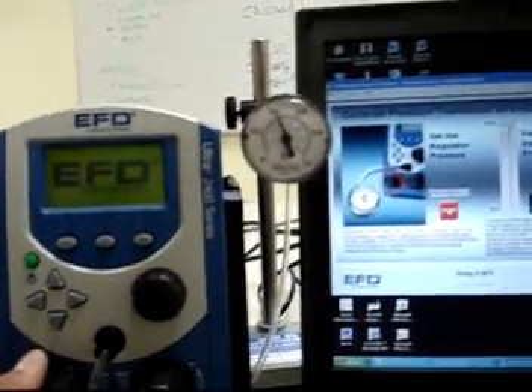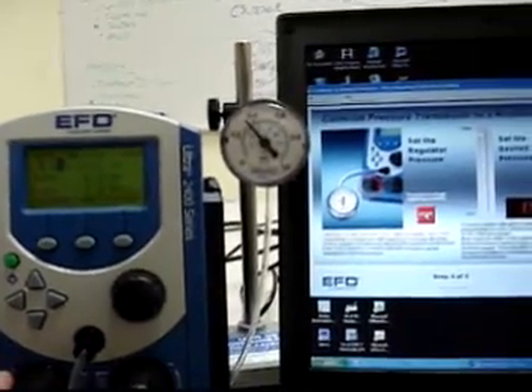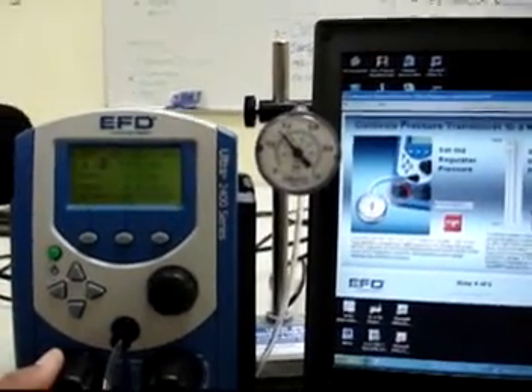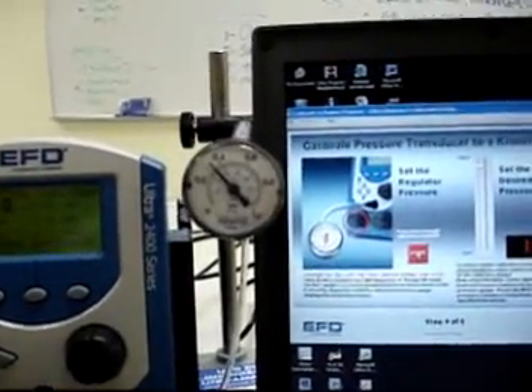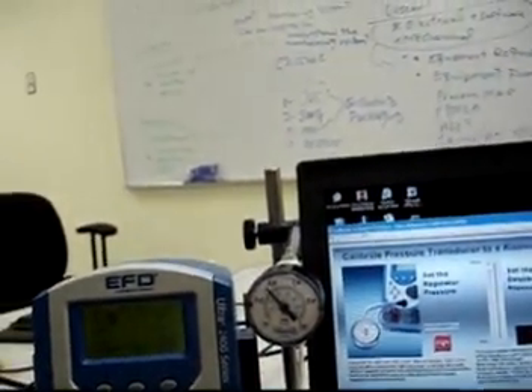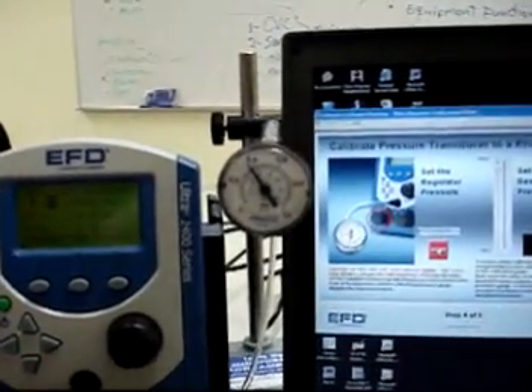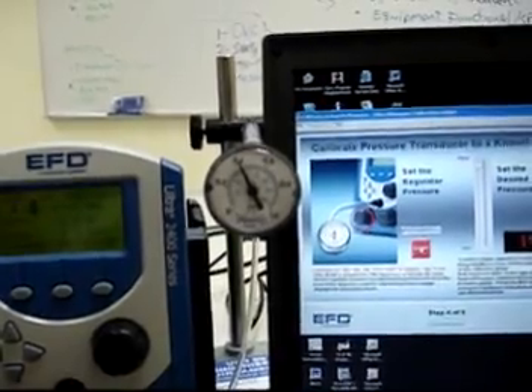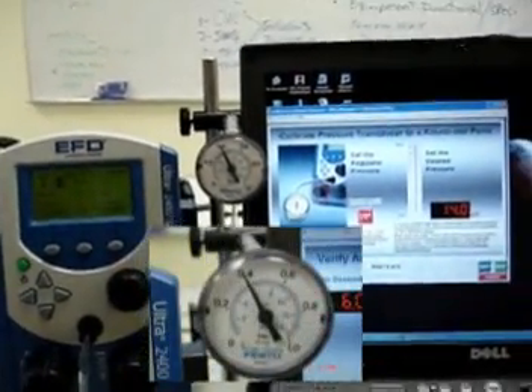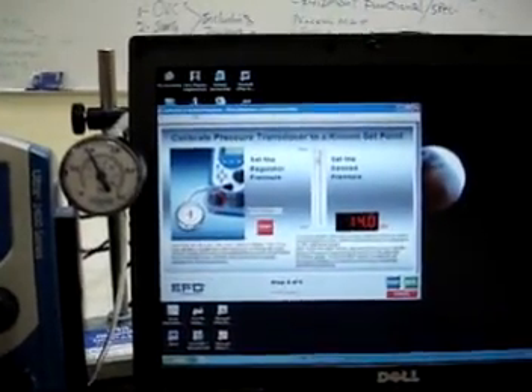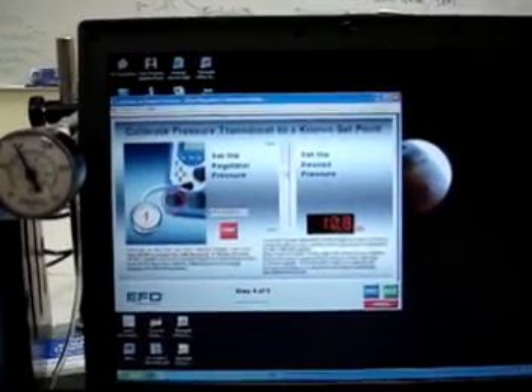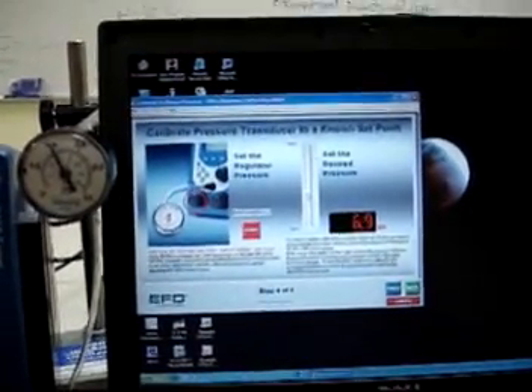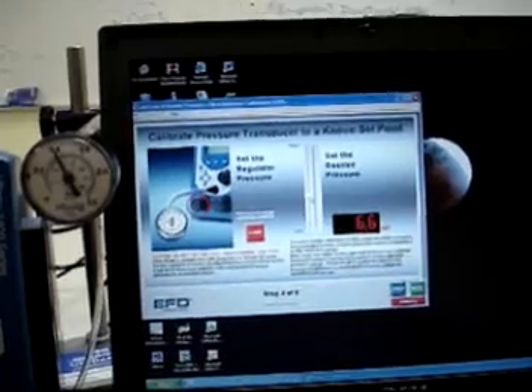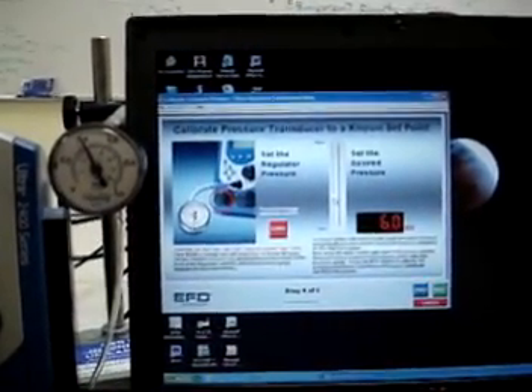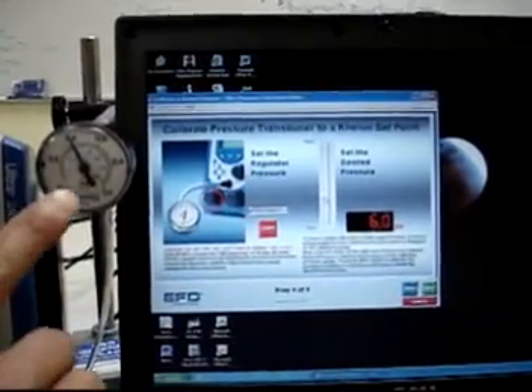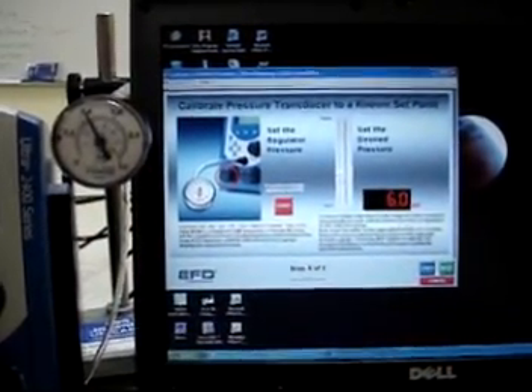Okay, now versus my calibrated gauge, I'm going to set about 5 psi, which is right here on my gauge, and then I'm going to set it to 6 so it is more clear. 6 psi is the blue numbers on the dial, and I will tell the software that I have actually 6 psi. 6 psi on the software and 6 psi on my calibrated gauge, and then I say next.